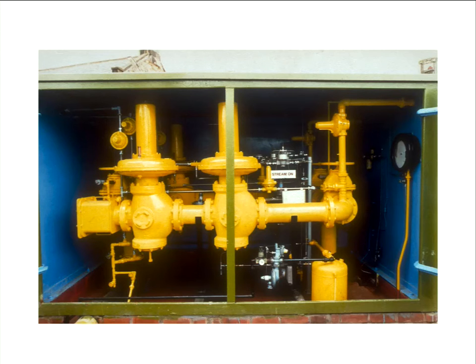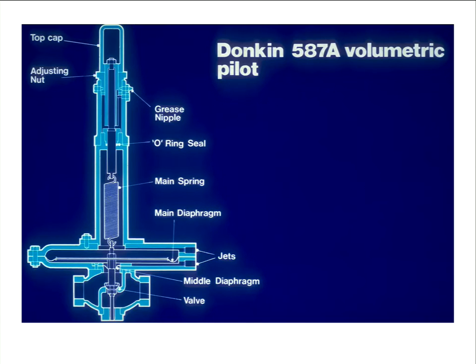But you can go a bit further. If you do need to manage your system more widely, you've got motorised springs. A lot of those were used on the old holder stations, the gas holders, where you might be flowing more gas into it during the day and less gas at night. So you were doing a lot more active control. I suspect there are fewer of those about these days. But you also want to think, what do I want to do if my interface fails? It could fail high or fail low. Do you want it to go open, closed, or is the best thing to stay where you are? Don't move, so freeze fail.